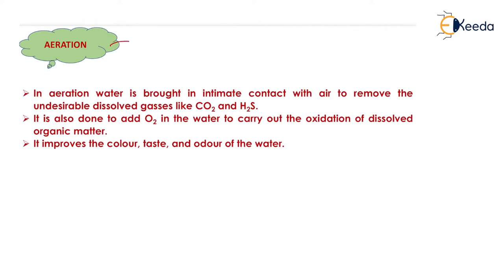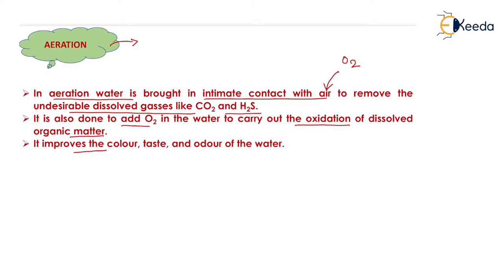The next process is aeration. Why do we need to aerate the water? To carry out the oxidation of dissolved organic matter. If we carry out the oxidation before the plain sedimentation tank, the efficiency of the plain sedimentation tank will increase. In aeration, water is brought into intimate contact with air, to remove undesirable dissolved gases like CO₂ and H₂S. It is also done to add oxygen in the water to carry out the oxidation of dissolved organic matter. Aeration improves the color, taste, and odor of the water.